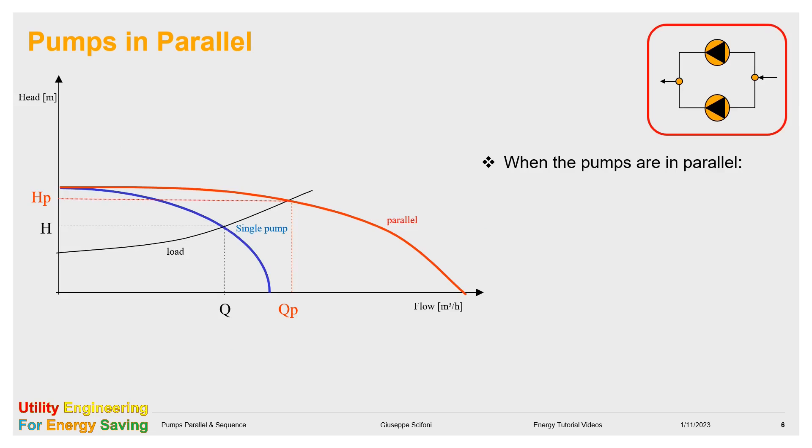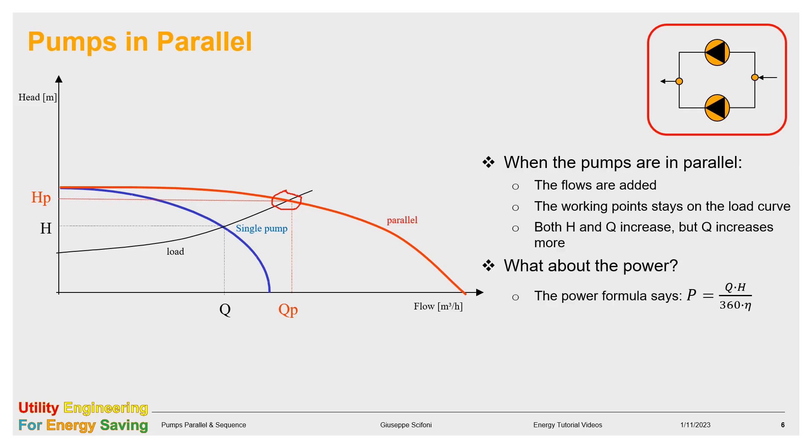Now we see how the parallel operation looks like. The flows are added. The working point is kept on the load curve, and moves into the right to match the new system curve, the right one. If the pumps are correctly chosen, Q increases more than H. The power is given by the same formula for the single pump, by using the new operation point HP and QP. Same as seen for the sequence, generally the power of the parallel is less than the sum of the powers of the single pumps.